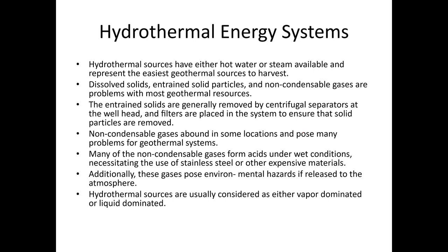The entrained solids are generally removed by centrifugal separators at the wellhead, and filters are placed in the system to ensure that solid particles are removed. Non-condensable gases abound in some locations and pose many problems for geothermal systems.